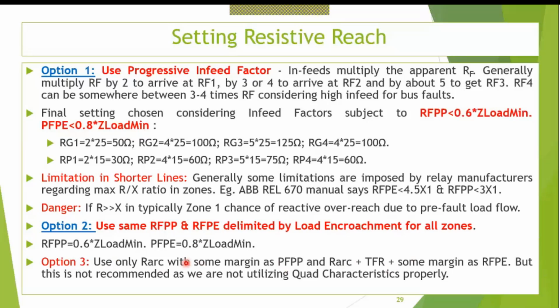Option 3 is the lower portion. Option 3 generally we don't use, because otherwise higher fault resistance faults won't be captured. If you use only Rarc and Rarc plus TFR outputting, then you won't be able to capture all faults. That's what I've seen from my personal experience.